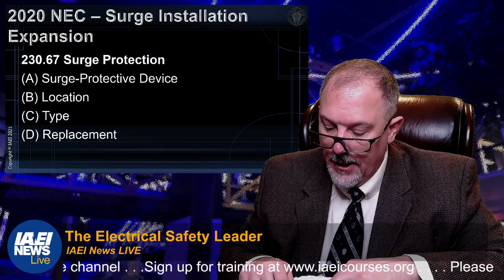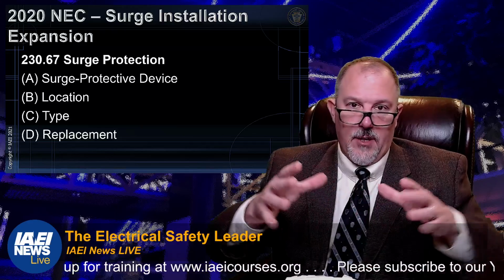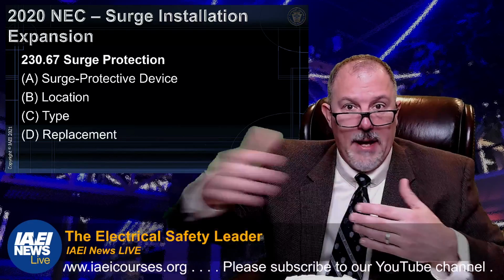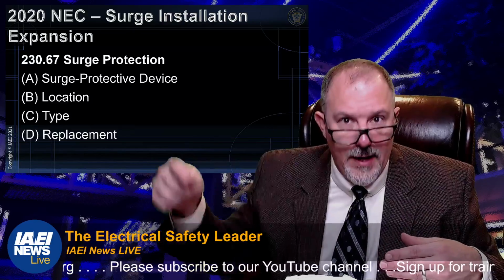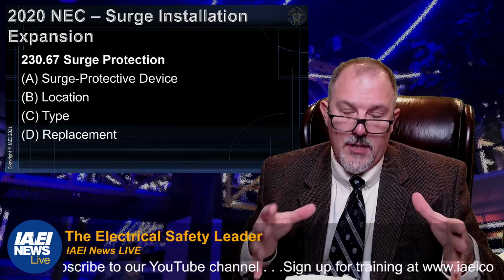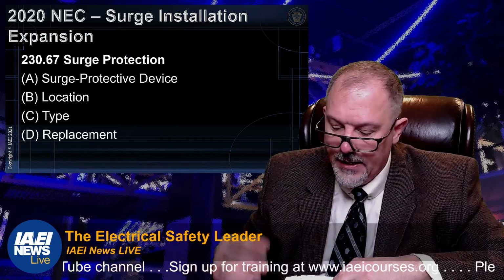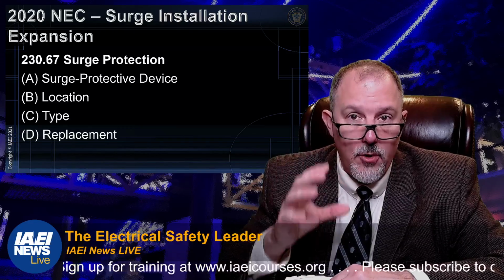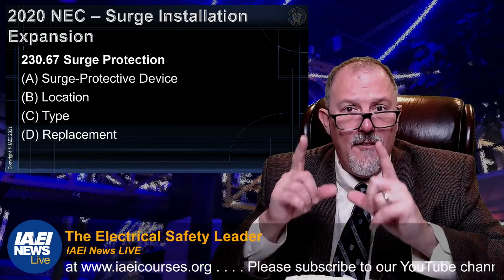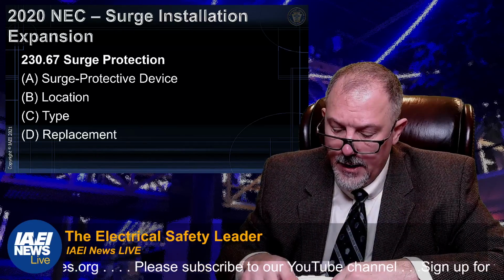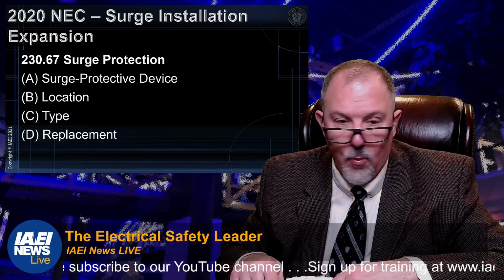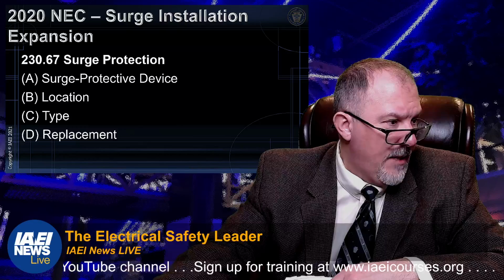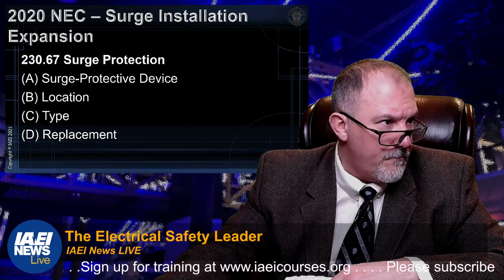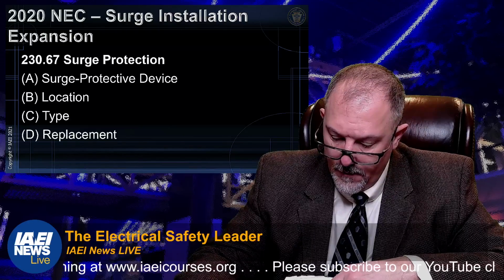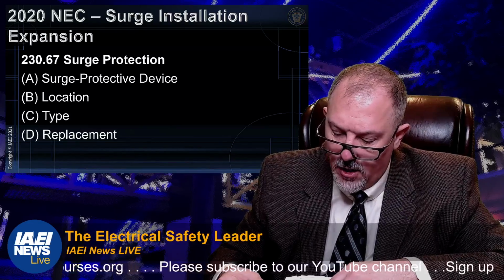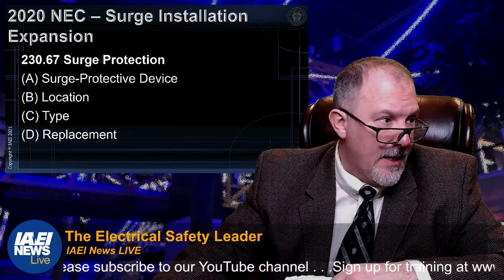And there is an exception. The exception basically is like when you have that meter stack or meter center outside, there's panel boards inside in each of the residences. You can put them at each of those panel board locations and you don't have to put it out there on the meter centers. So you can put it at the first level of distribution downstream. Now I will say location of the SPD is critical, as close to the bus as possible. You want to keep those lead lengths very short. Very important to do that. And then the replacement types should be SPD types 1 or type 2. And then replacements. Where service equipment is replaced, all of the requirements of this section shall apply. So they're picking up replacements.